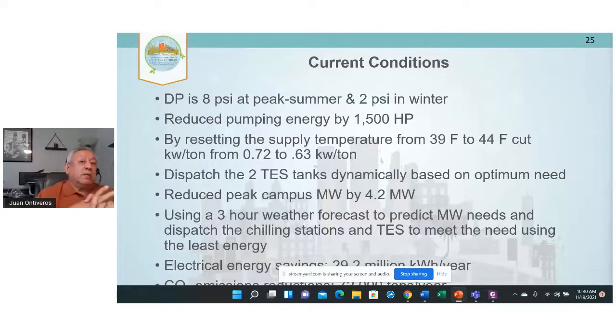Then we said, okay, I produce power, I produce cooling, I produce heating. We did a weather forecast. We did a linear regression of weather and cooling load and power loads for 3 years, and we developed regression curves. So we can do a pretty realistic projection of weather for 3 hours, and we use that to predict our power load. Then we use that to dispatch the chilling stations and the TES to meet it.